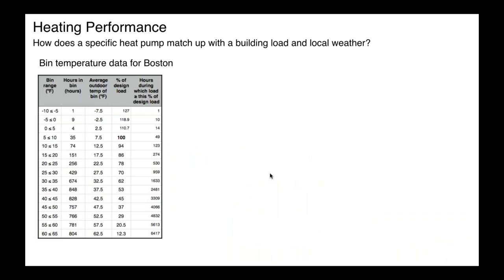Now, again, for a specific case in Boston, when we're dealing with air source heat pumps and performance, we have to know what is the outdoor temperature range and how many hours is the outdoor temperature, for example, between 5 and 10 degrees or between 35 and 40 degrees. So you can get this data. ASHRAE has this data. Some of the Manual J's, the ACCA Manual J's, actually have an appendix that has this data. But it's called bin temperature data.